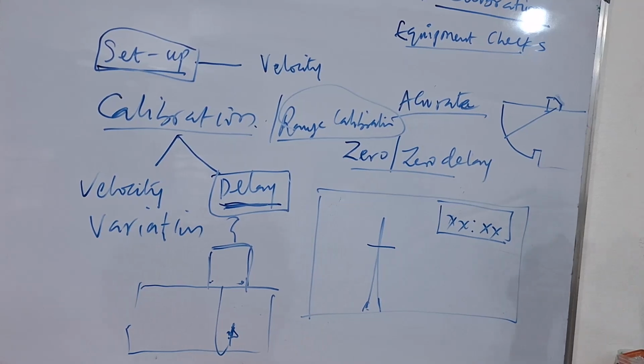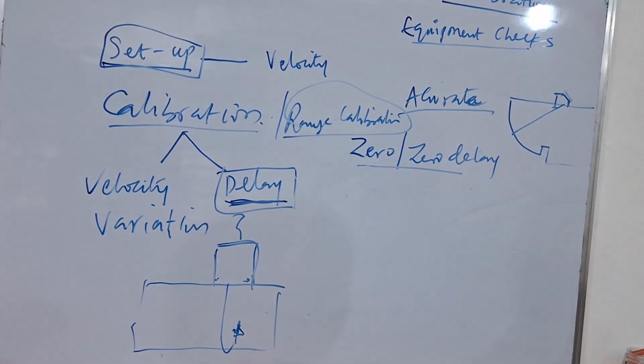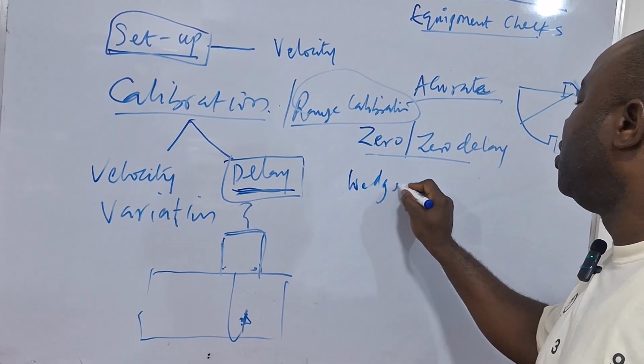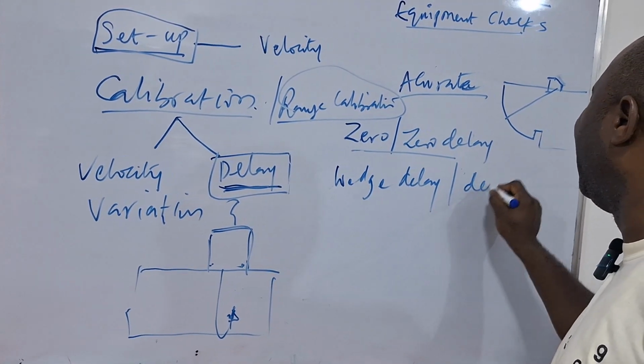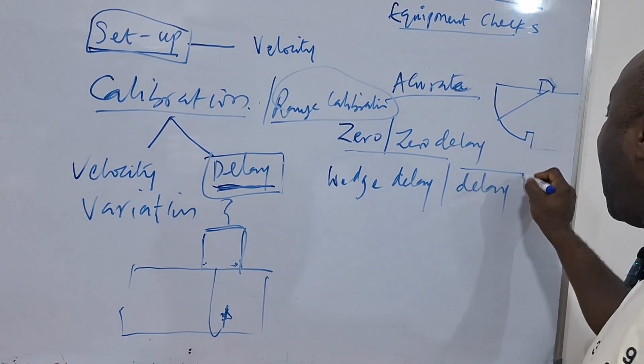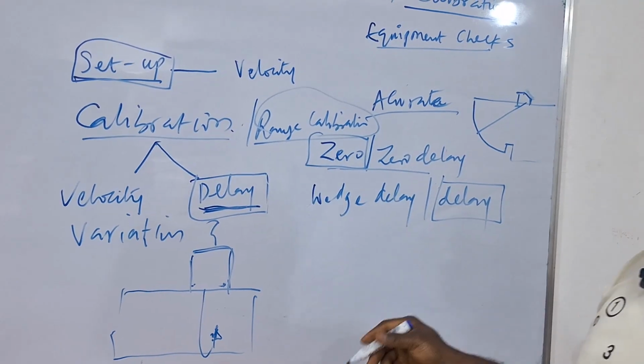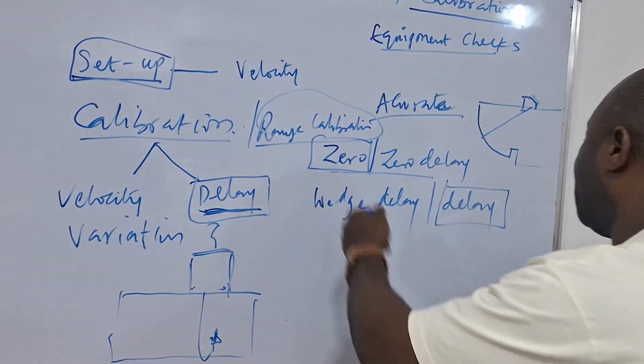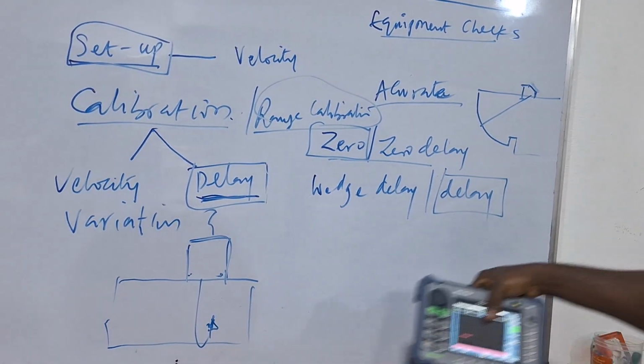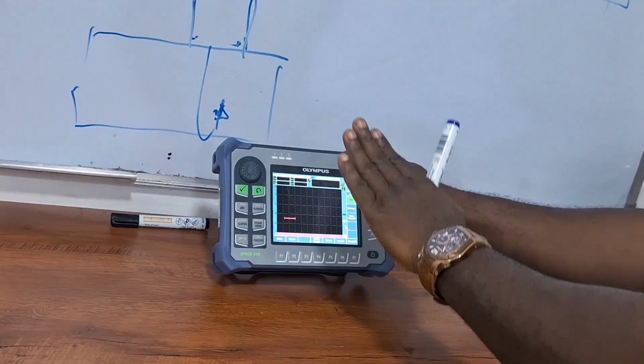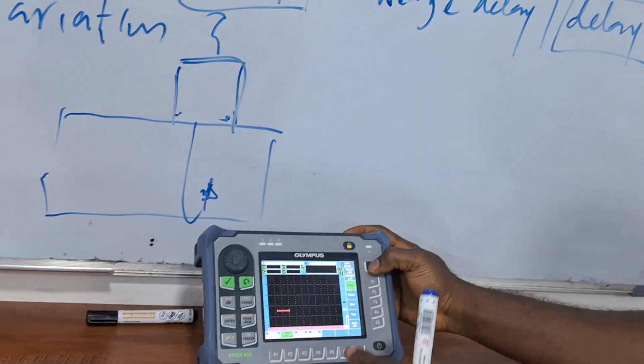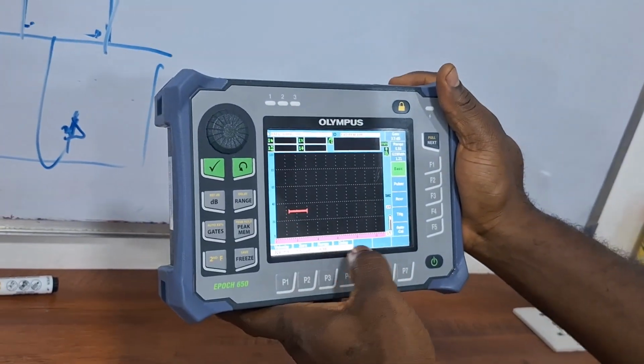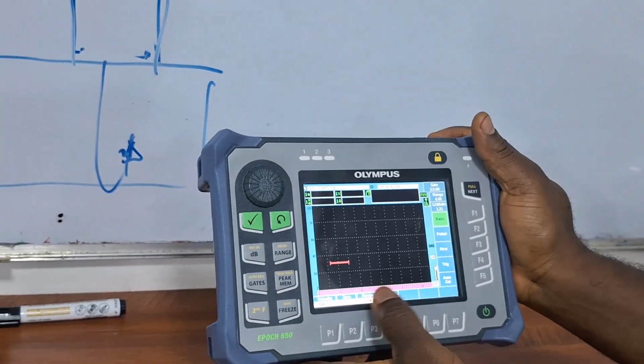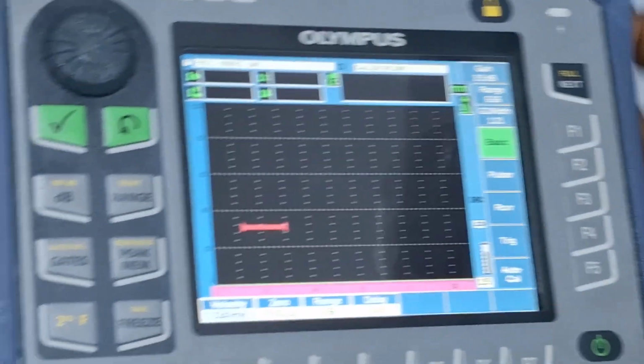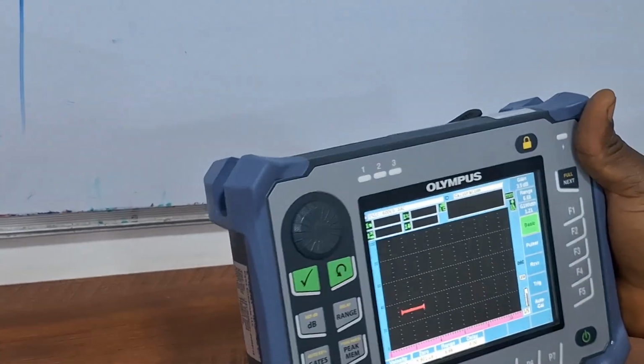Another way of compensating for your delay is what we call the wedge delay. Some equipment will call it wedge delay, or some will simply call it delay. In some other units, it will have a delay and also have a zero. So to get your final calibration, you need to adjust your zero and also adjust your delay. If you look at this Olympus EPOCH 650, in the basic calibration, you are going to have both. As you can see, you have the zero and you also have the delay. This compensates for the delay variation and the velocity variation.